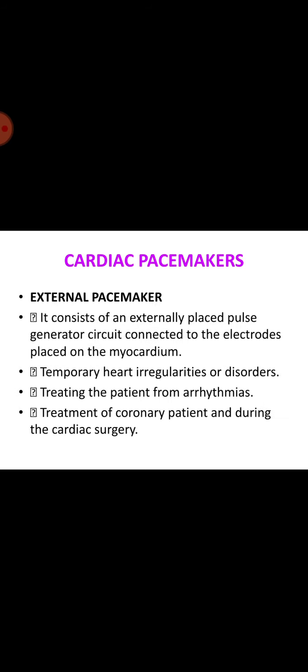There is no external connection for applying power for the internal pacemaker, so the pulse generator should be completely self-contained with a battery which is capable of operating continuously for a specific period. And the external pacemaker consists of an externally placed pulse generator circuit connected to the electrodes placed on the myocardium.